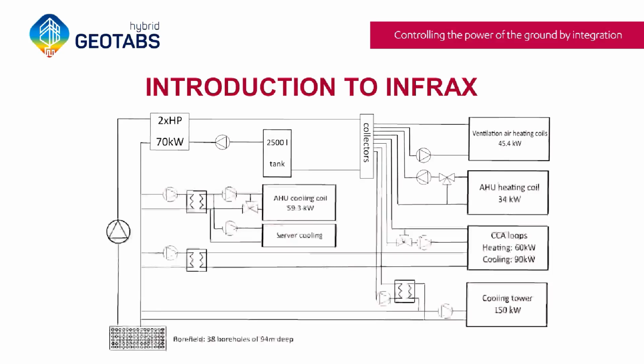This is a schematic overview of the HVAC of the system. So everything is more or less built up around the geothermal bore field, where we have a main circulation pump that drives this circulation loop. And the first thing along this line is two geothermal heat pumps of 70 kilowatts each. And actually there's a bypass here also, which allows you to bypass water through here, which can be used for passive cooling. So the passive cooling is either for server rooms or the air handling unit cooling coils, or it can be used directly for cooling the concrete core activation. So concrete core activation can either be used for cooling or for heating. For cooling, it's through the geothermal bore field, and for heating, it's going through the geothermal heat pumps.